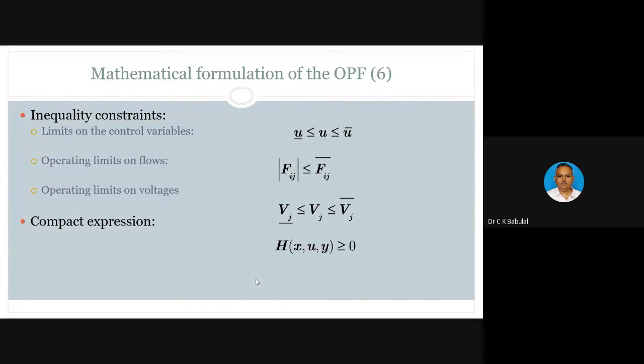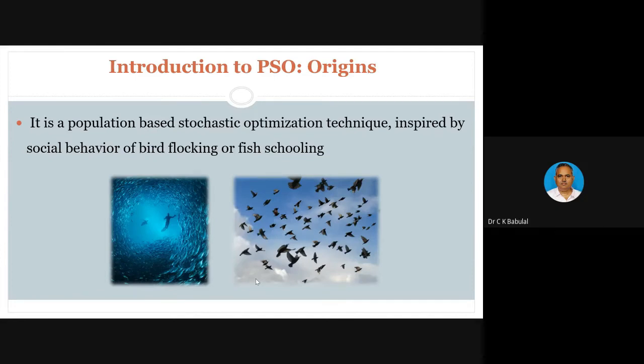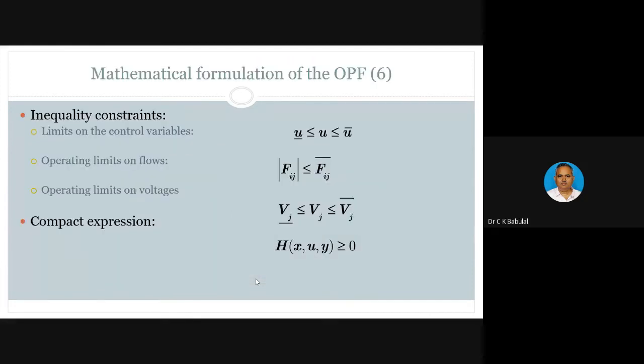So there are limits on the generation and limits on the transmission line. Every transmission line is designed for flow of a certain MVA, so there is a limit for power flows in the transmission line, called the thermal limits of the transmission line. And operating limits require that you must operate your power system within possible ranges of voltages, thus forming the voltage limits.